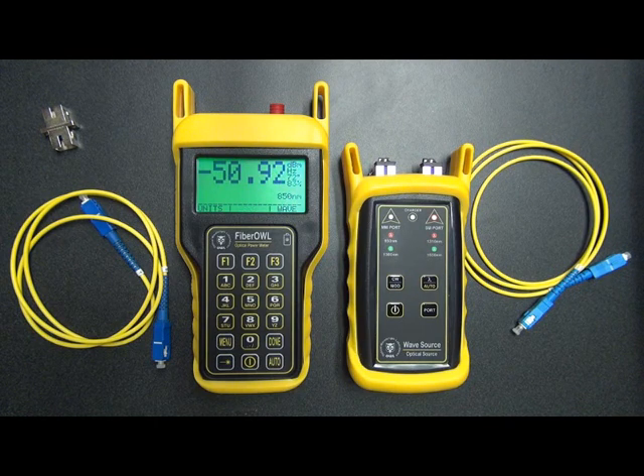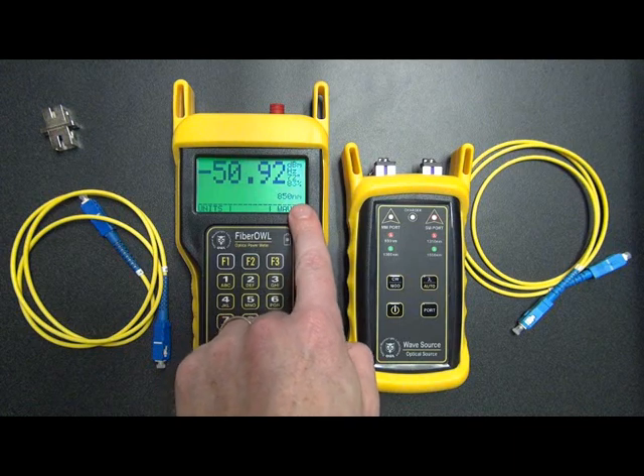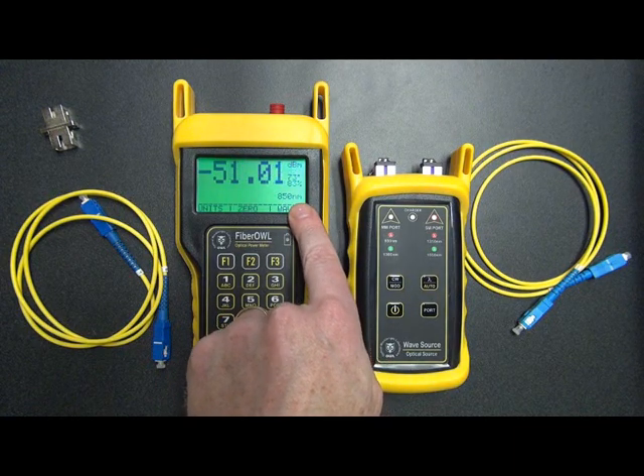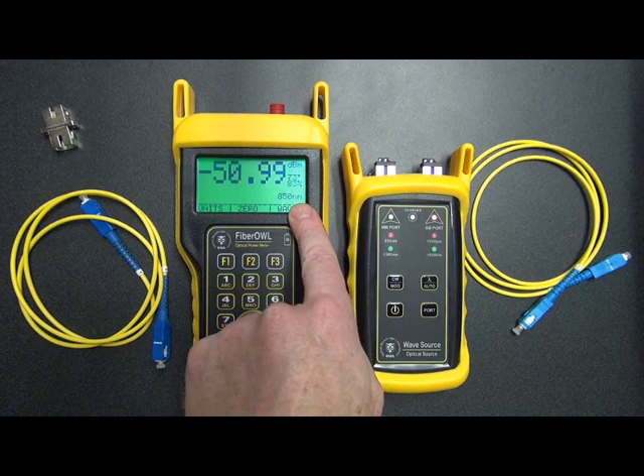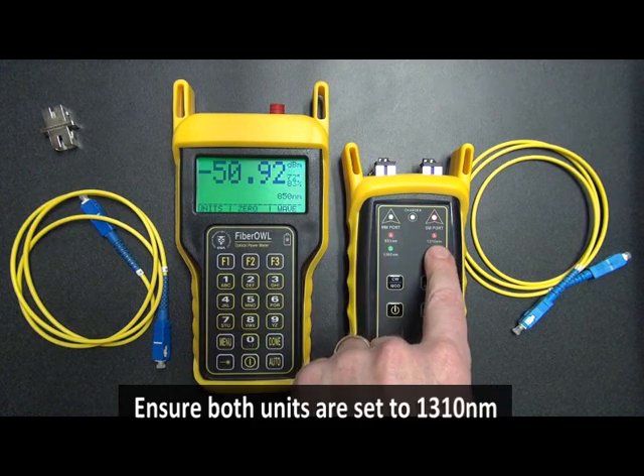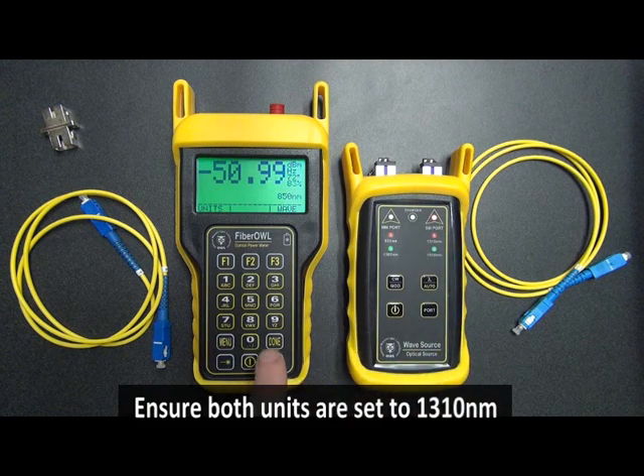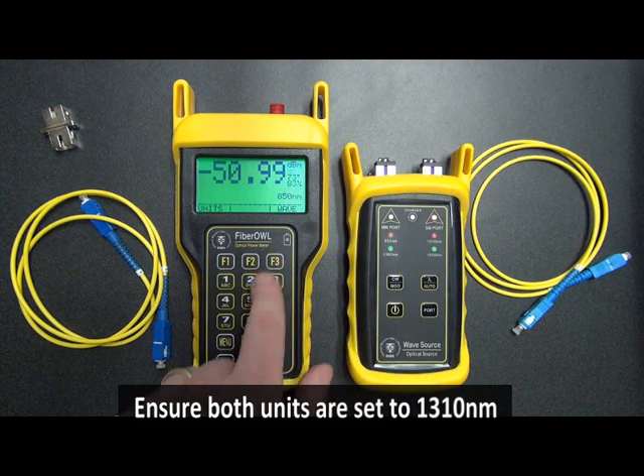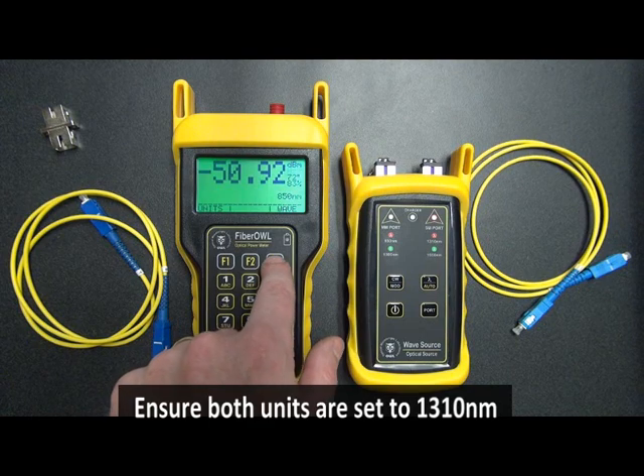You'll notice that the wavelength is set to 850 nanometers. Since we're going to be checking single mode, we need to switch to the single mode wavelength. So the light source is set to 1310 nanometers, so we also need to switch the wavelength on the Fiber Owl. We do this by pressing F3.